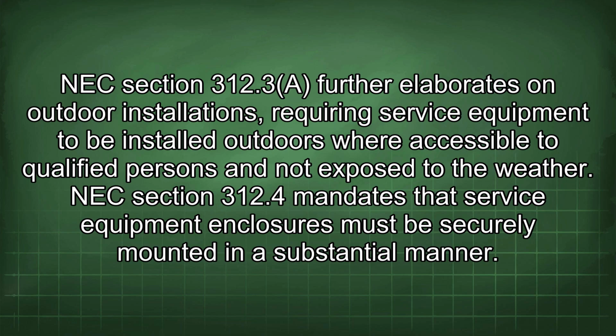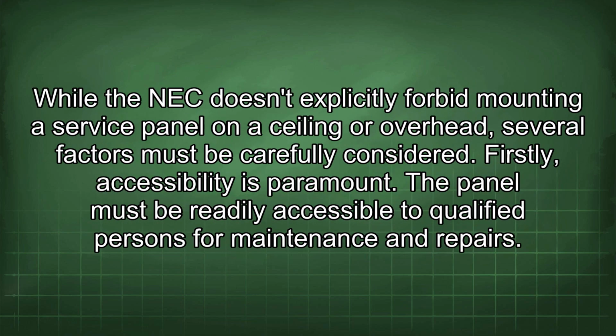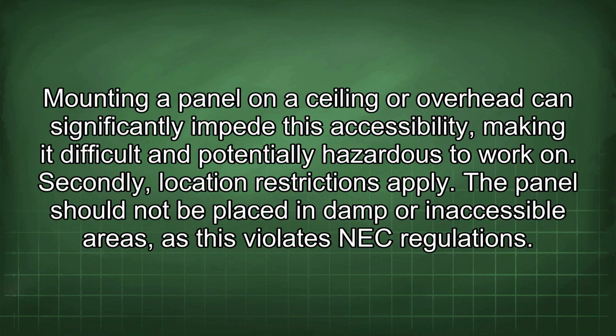NEC Section 312.4 mandates that service equipment enclosures must be securely mounted in a substantial manner. While the NEC doesn't explicitly forbid mounting a service panel on a ceiling or overhead, several factors must be carefully considered. Firstly, accessibility is paramount. The panel must be readily accessible to qualified persons for maintenance and repairs. Mounting a panel on a ceiling or overhead can significantly impede this accessibility, making it difficult and potentially hazardous to work on. Secondly, location restrictions apply.